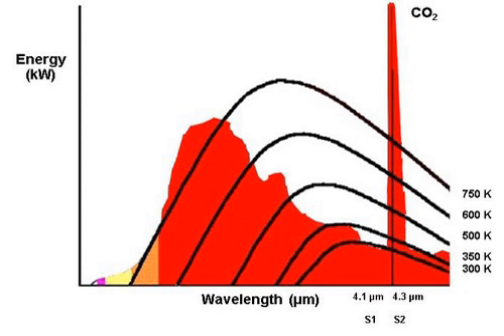Some infrared detectors have an automatic detector window self-test, but this self-test only monitors the occurrence of water or ice on the detector window. A salt film is also harmful, because salt absorbs water. However, water vapor, fog or light rain also makes the sensor almost blind, without the user knowing.